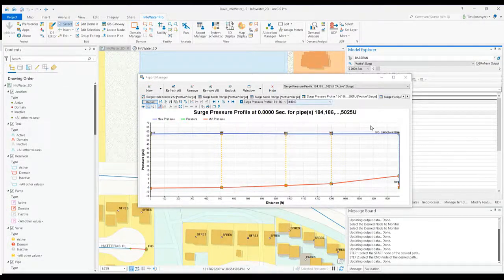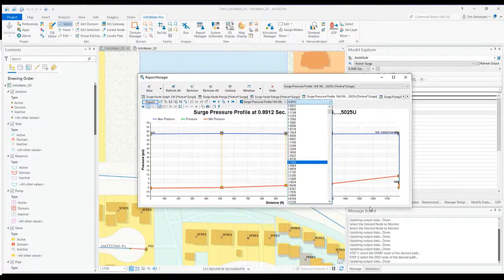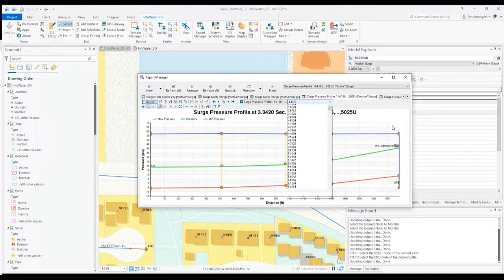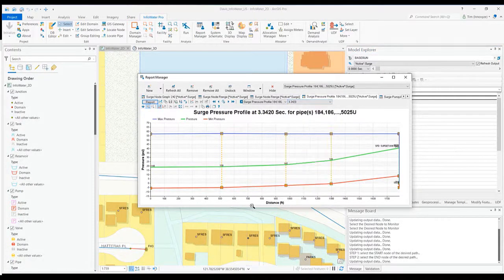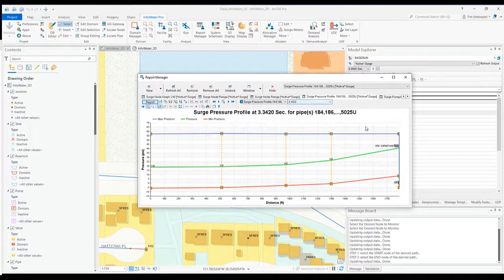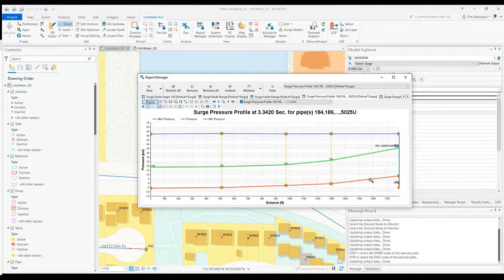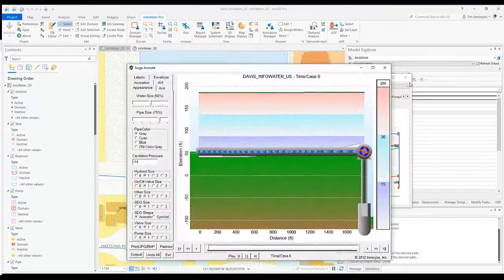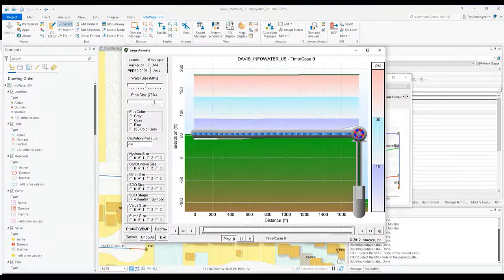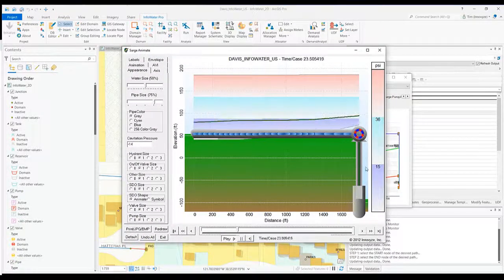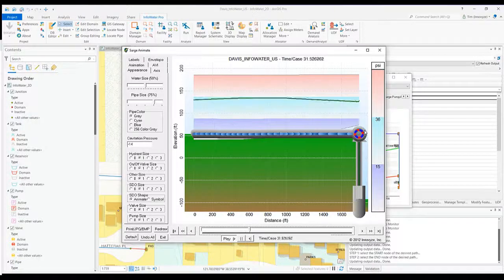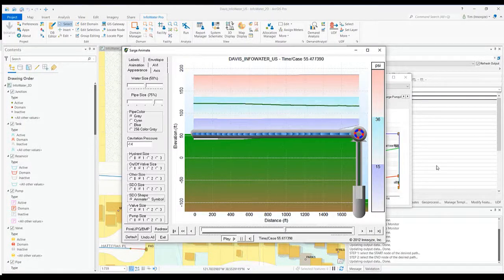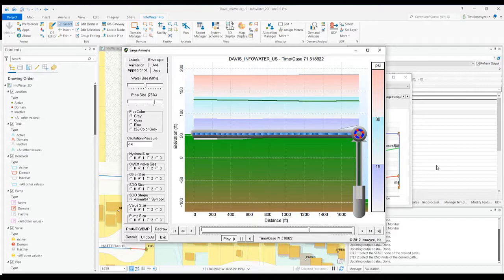Here's my pressure during that particular time step, three seconds, max, min. Again I can see that surge event animated if I'd like to. If I play this, let's see if we have cavitation now. Again, much less, and it looks like we don't have quite the cavitation as before.